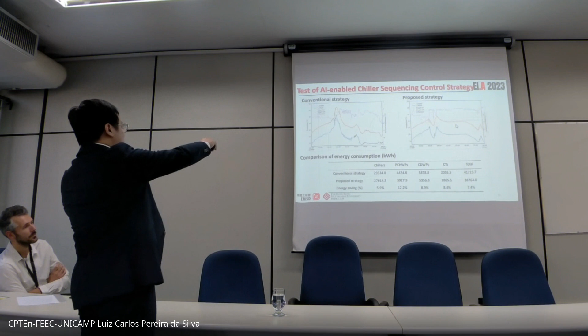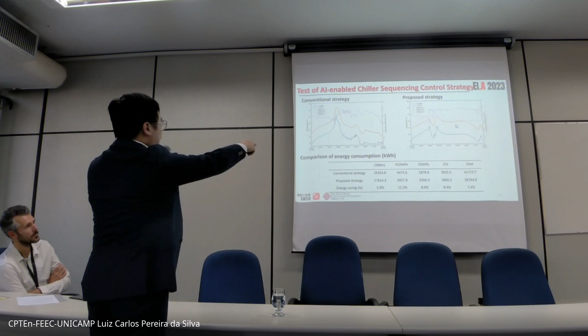In the conventional strategy, we can see that in the morning time, the chilled water supply and return temperature was really high, which would negatively affect the indoor environment condition. In the afternoon, we can see frequent on and off cycling of the chillers, which is also not good.